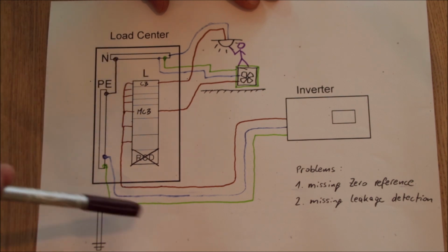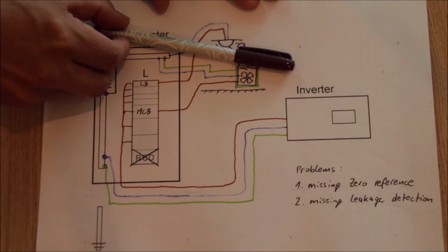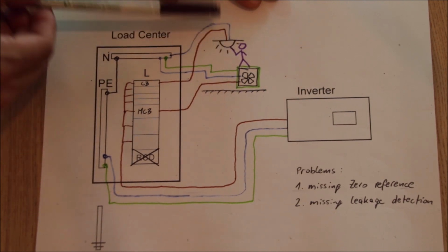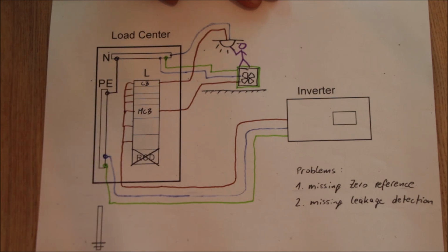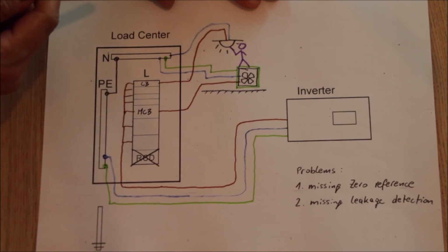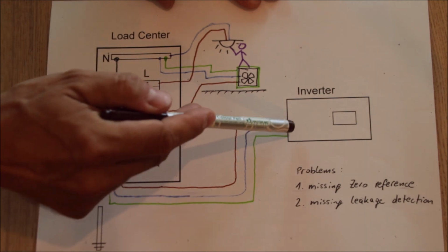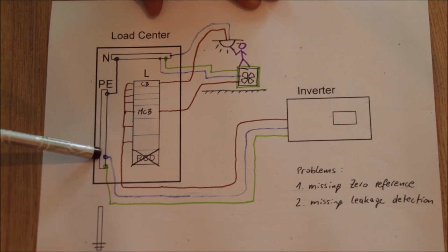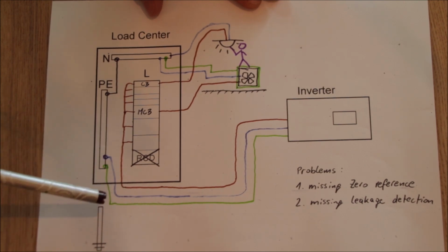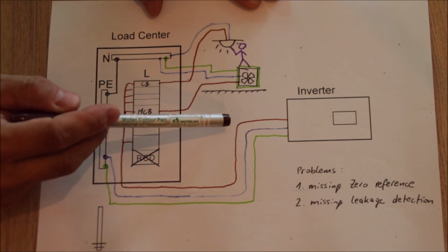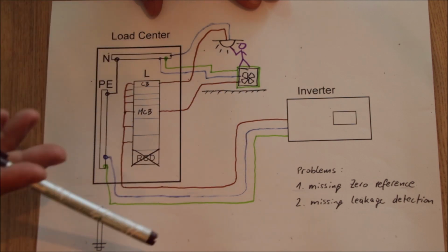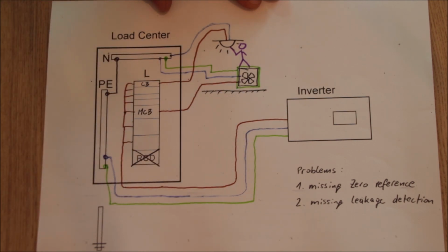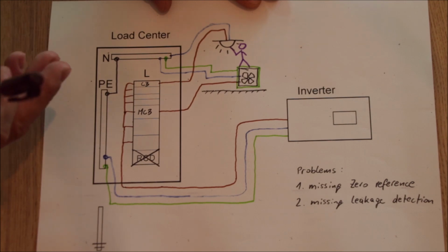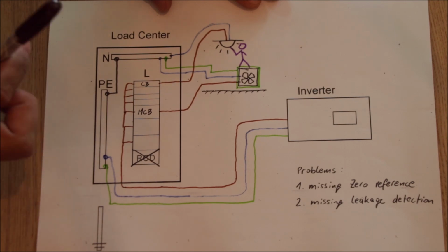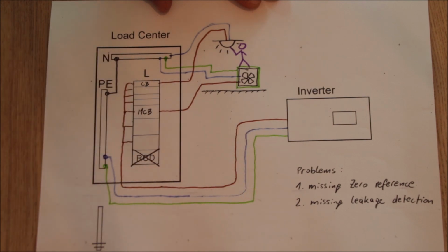So if you look now at this setup here, forget initially this one here, what I was drawing with the human and the light fixture. We will talk about this when it comes to what can happen in this system. You have your L and you have your N and PE without reference to ground. So that means that in your setup here you only have L and N, because PE does not exist, it's just parallel cabling. What is the first problem in this setup? Well, the first problem is, if you have looked at other videos on my channel, we don't have a zero reference.